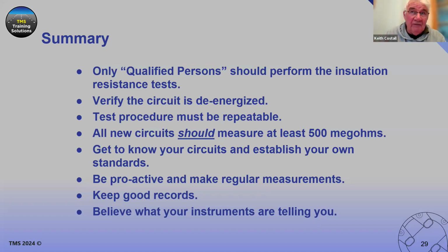Calculating that using Ohm's law at the 5,000 volt design criteria gives you the minimum acceptable insulation resistance for that particular circuit. Then you decide what you're going to do from a maintenance viewpoint when you're going to look for the possible fault in the fault diagnosis technique. Basically, a rule of thumb is that, depending whether it's a wet location or a dry location, at 2 times the calculated value, or 5 times, or you may decide 10 times the calculated value, you start to look for that fault. Mend it before it breaks, basically.